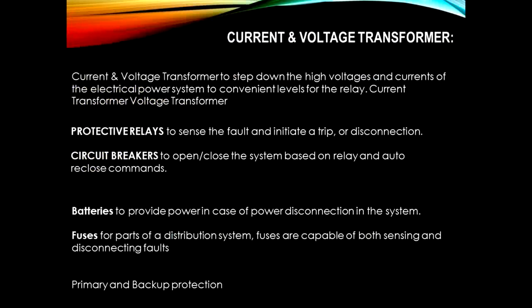The same thing has been explained here with current and voltage transformers -- these are things you can use for measurement as well as protection. The starting of the substation is with CT and PT: CT is current transformer, PT is potential transformer. CT and PT measure the current and the voltage, and at the same time protect if high current flows. So you will be using CT and PTs for protection as well as metering usage.